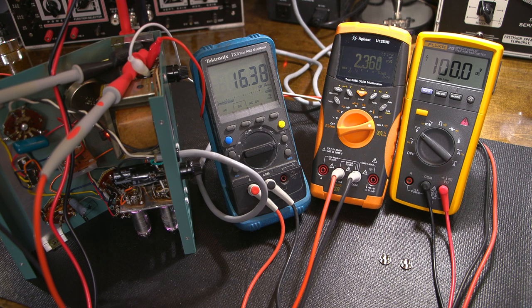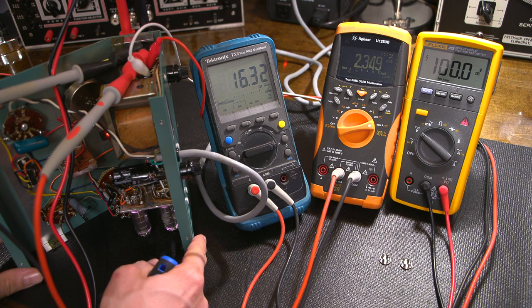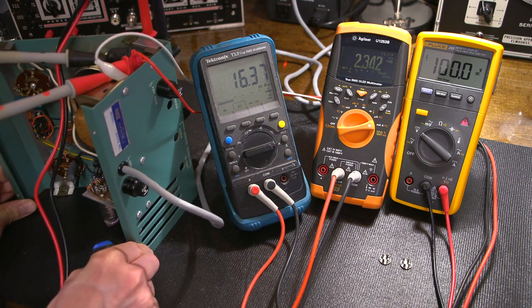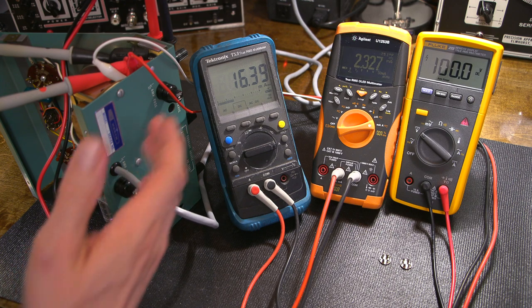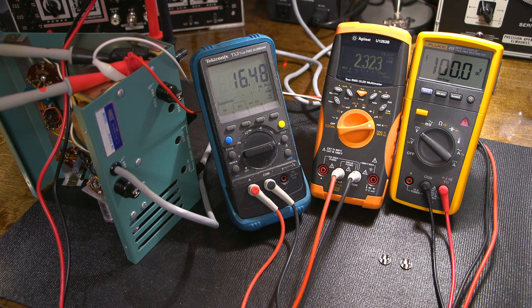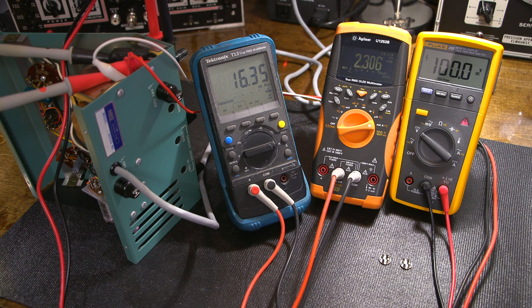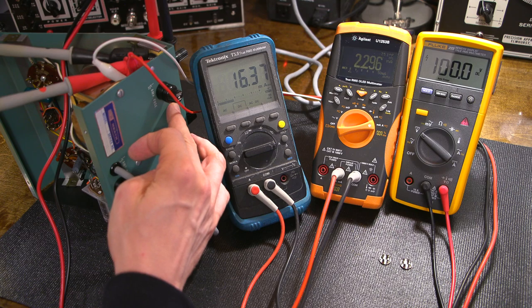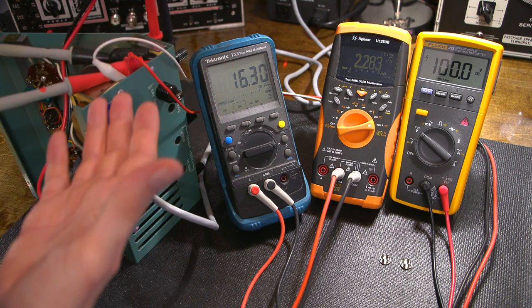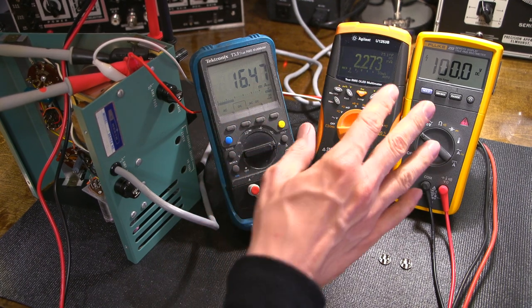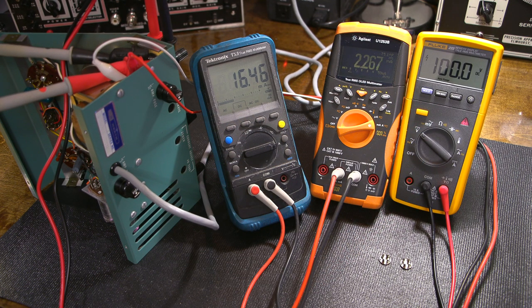So technically what I need to do is let this stabilize the best that I can. I'll just move this back over this way. I'll let this stabilize the best that I can with the case off. So I'll let this run for quite a while. And what I'll do is adjust everything as close as I can get it. And then the only thing I can adjust after that point really is the calibration here, because it doesn't require me to have any current meters attached inside the unit. Again, I can't get into the unit with the case on with the two current meters. So I'll set these as close as I can, and then I'll adjust the calibration, which sets the output right here.